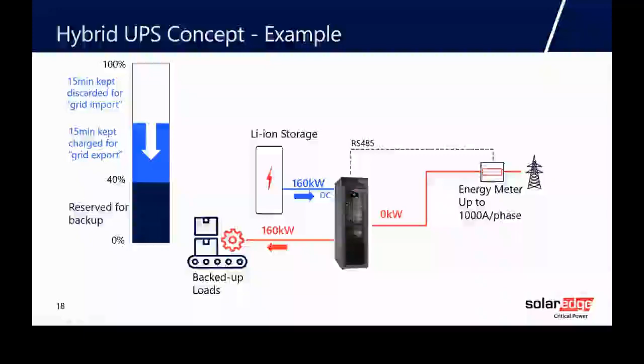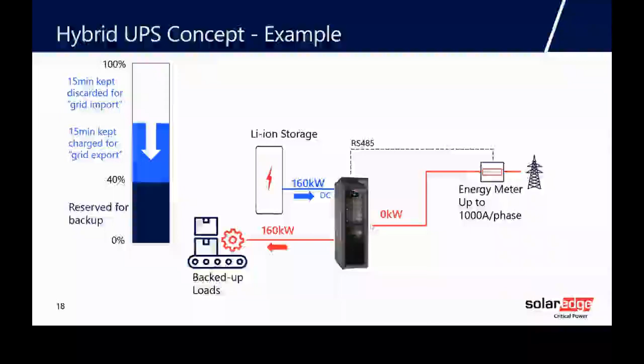It was mentioned earlier that you need response within 30 minutes. Well, these UPS systems can respond in as long as it takes to switch on a switch—a few milliseconds. They can just instantly turn off their rectifier, and then basically they're invisible on the grid. Also, because we're not exporting power back to the grid, we don't need all the complications of G99 relays and all that testing. So we're basically just turning off a switch in simple terms, and we can do that very quickly. I think frequency response is where they need things done very quickly.